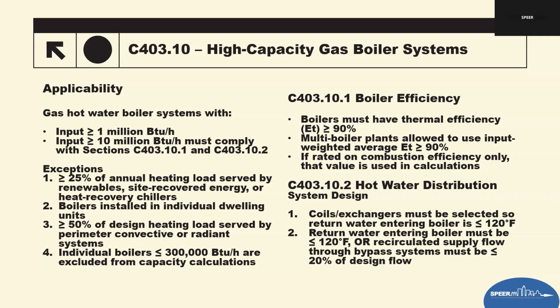So, plan review tips for that. Confirm boiler capacity falls within that 1 to 10 million BTUs per hour range. Verify thermal efficiency is greater than or equal to 90% in submittals. Check multi-boiler efficiency calculations for correct input weighting average. And then review coil and heat exchanger schedules.